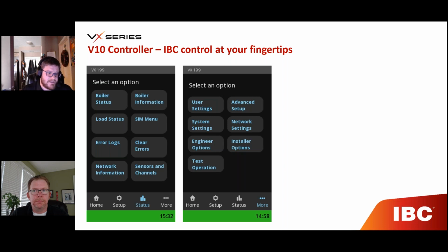Our favorite button is test operation, which is great for calibration or troubleshooting. It's a place to play with BTU output and see flame signal, temperature, supply and return temperatures—all the information you need to calibrate is in one convenient screen. You can ramp the unit up and down based on your requirements at the time: high fire, low fire, mid fire, whatever you want to do.